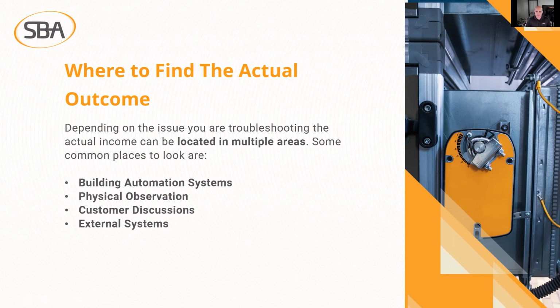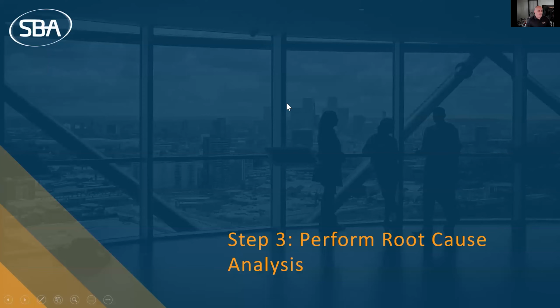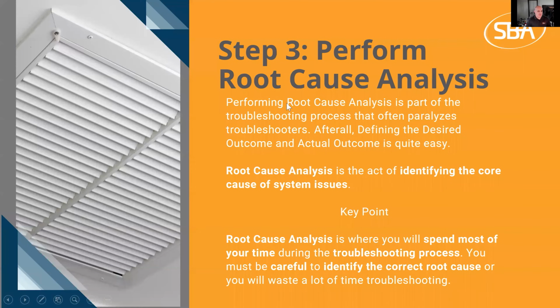We can check our building automation systems graphics, alarm reports. We can do physical observations, which I highly recommend. We can go and have discussions with our customers, and we can look at external systems for third-party integrations, things like that.